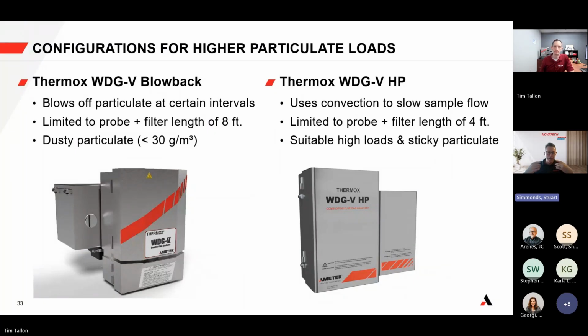What's interesting from an industry point of view is almost everybody else tends to always put a filter on the end of their probe, even under regular circumstances with close-coupled ones. I think, and perhaps you could verify this for me Tim, it's because most other people have very small bore tubing, and their analyzers run directly through the process. Their aspirator sucks right through the process, through their sensors, and the tubing is quite small. So they're terrified about getting anything into the analyzer.